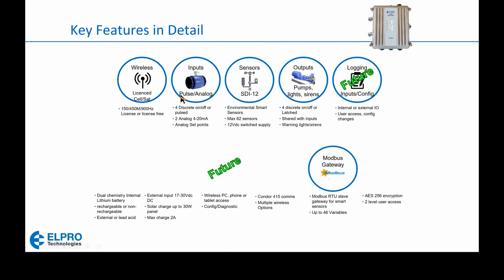Okay. Analog inputs and outputs. We've got the 2 analog 4 to 20 milliamp inputs. These are compatible with both 2 and 4 wire type devices. So the radio can provide a 24 volt output for powering a 2-wire 4 to 20 milliamp transmitter.